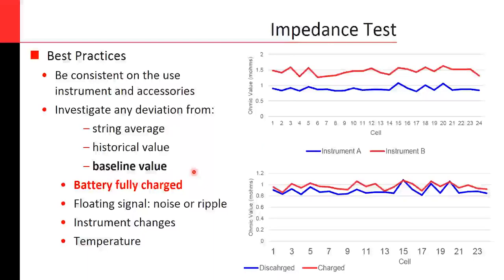Here in this slide to the right, I have some examples of what can happen if you are using two different instruments, or instruments that are applying two different signals to obtain the result. So you can see in this very first one that instrument A provided this value for each cell, and instrument B gave you these results. It's more than probably 50% of change, and if you are not aware that you are using a different instrument, you might think you have a problem in the battery. That's one of the consequences of not using the same type of instrument and accessories.